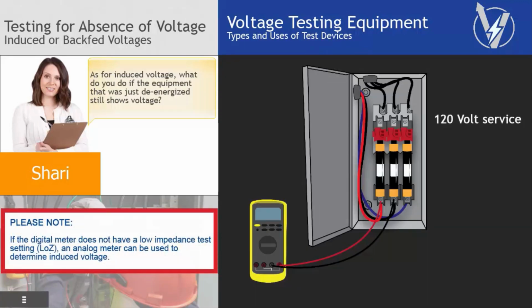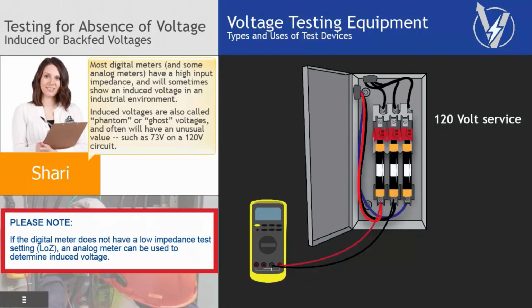As for induced voltage, what do you do if the equipment that was just de-energized still shows voltage? Most digital meters and some analog meters have a high input impedance and will sometimes show an induced voltage in an industrial environment. Induced voltages are also called phantom or ghost voltages and often will have an unusual value, such as 73 volts on a 120 volt circuit.